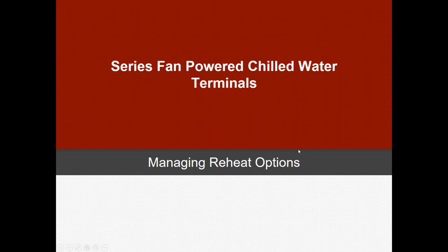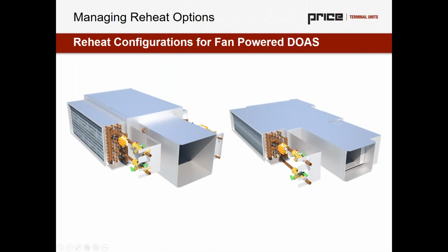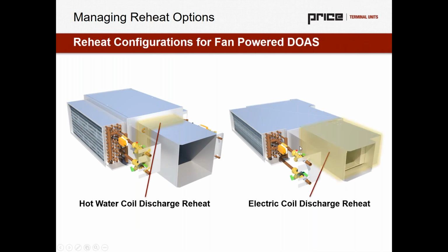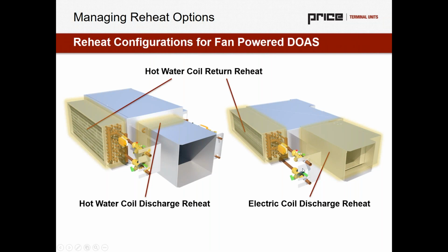So the next thing I want to look at, especially when we're considering the combination of this equipment, is the ability to manage reheat options. I know chilled beams can provide reheat with an interlaced coil, one face coil with reheat circuits running through it. But I think the other benefit of doing a hybrid style of system is all of the reheat options that are available on these fan-powered chilled water terminals. So whether you want hot water heat or electric heat, there's different options at play. Electric heat can be offered on the discharge in either staged or modulating styles of reheat. We can see a typical discharge hot water coil, and then more importantly, especially for your market, I think that return reheat coil provides some significant benefits.